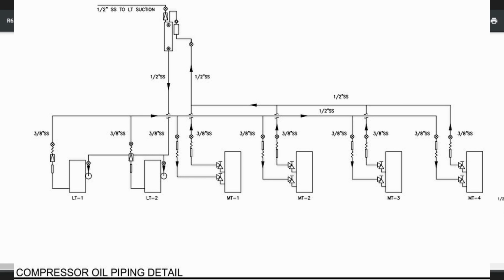Doesn't hurt anything. And then when the low stage compressors run out of oil, get low on oil, they both have a float on them, and the float opens and we fill the crankcase of the low stage compressors. The oil is always moving in these systems from the low to the medium and back and forth. And it's very important with this type of compressor that you don't overfill a compressor.